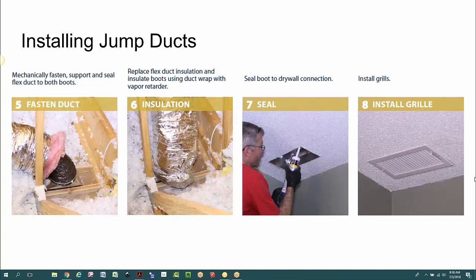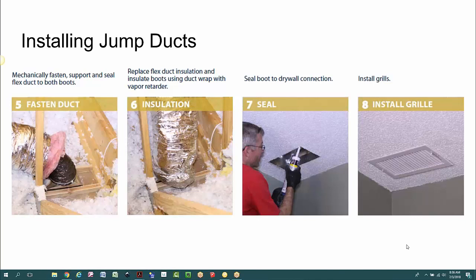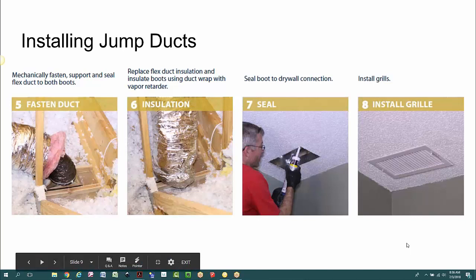And Matt, typically, if it is creating static pressure, a lot of times that's where they've got the furniture or something blocking the registers. You're probably not going to be putting in transfer grills and stuff at that point, I don't think, but it could, I guess, still with the pressures building up in the room. The biggest thing with your static pressure, Greg, would be blocked or plugged registers and grills. So that'd really be a matter of unblocking them.